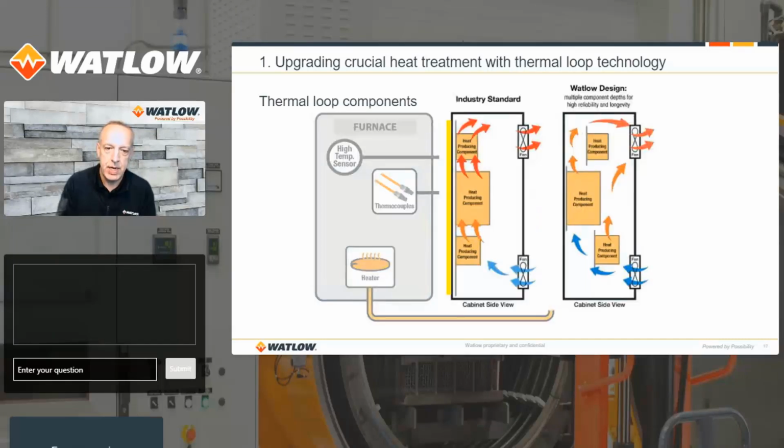And then if we look at another slide, more recently we started utilizing systems thinking and a three-dimensional view of the panel. We know when instruments get hot, they either don't perform or you have an impact on their overall life. It's pretty common in a heat treat department where the ambient air temperature is generally raised. Cooling of the cabinet is critical, and only a fraction of cabinets have some form of true air-conditioned cooling. All other panels typically have inexpensive fans shuttling heat around.